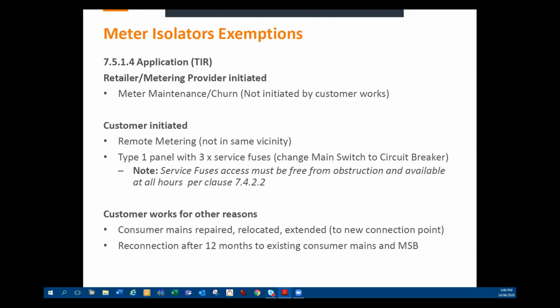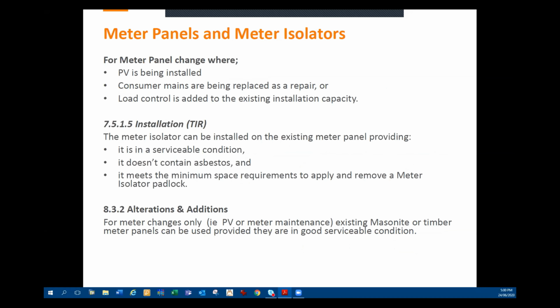There will be certain circumstances that they do, but also if it's a reconnection after 12 months to existing consumer mains and main switchboard, if there's been no changes to any of those and it's a straightforward reconnection, then there's no requirement to install a meter isolator. So with meter panels and meter isolators, we'll continue on with that.